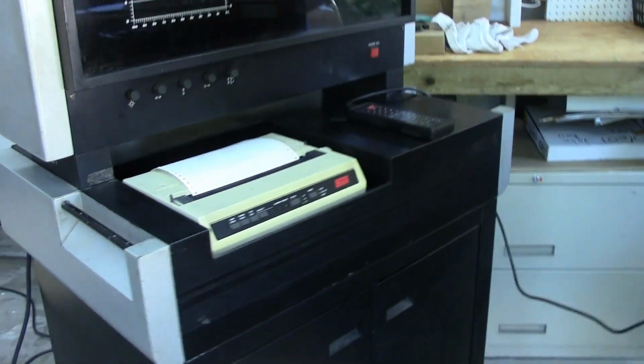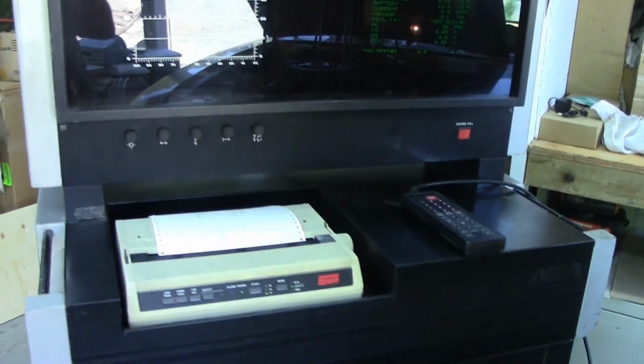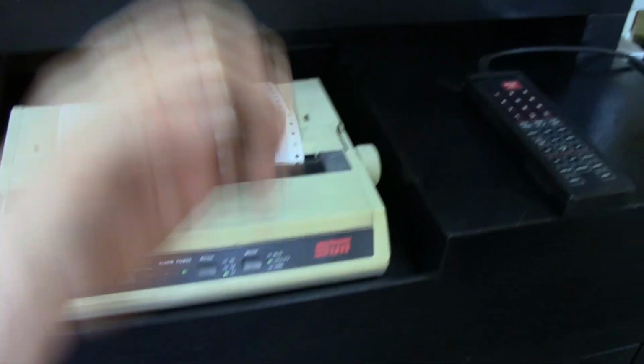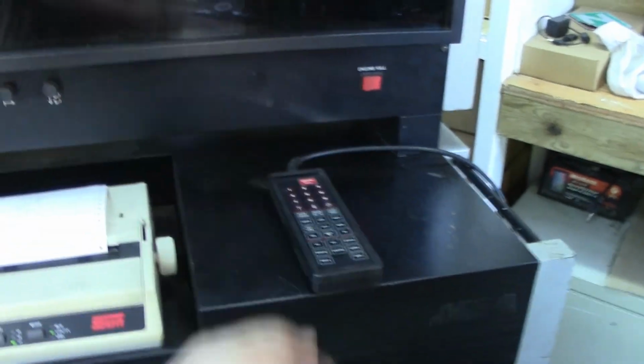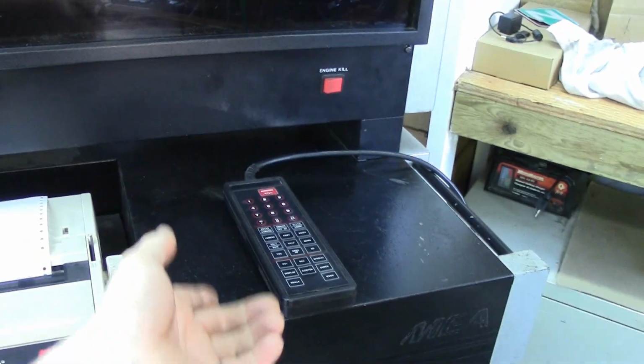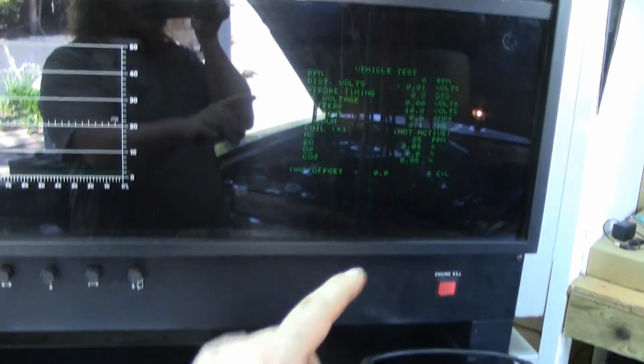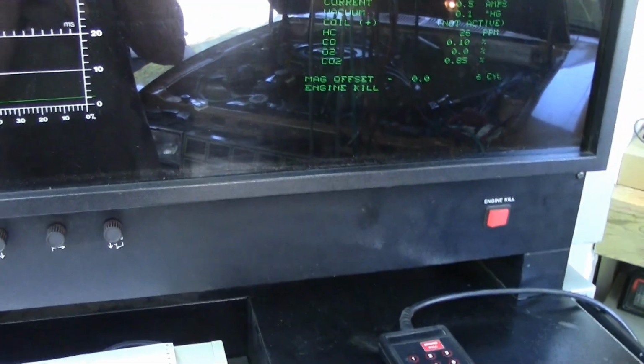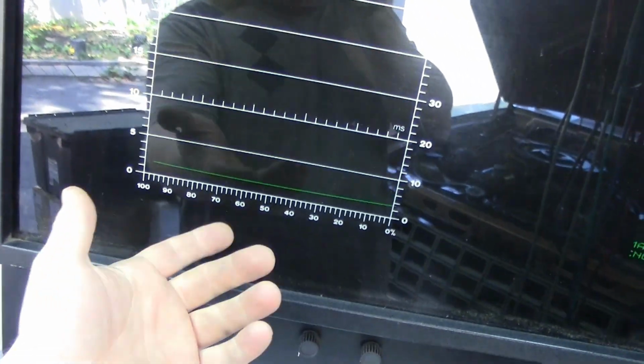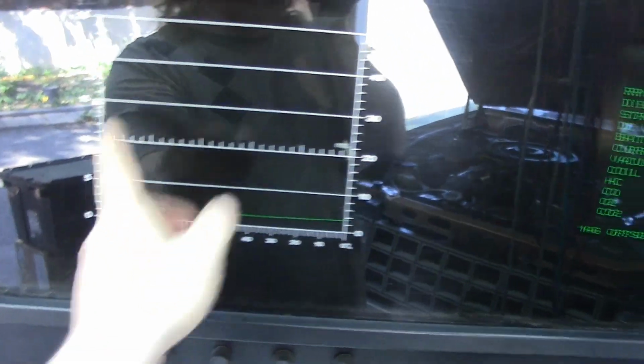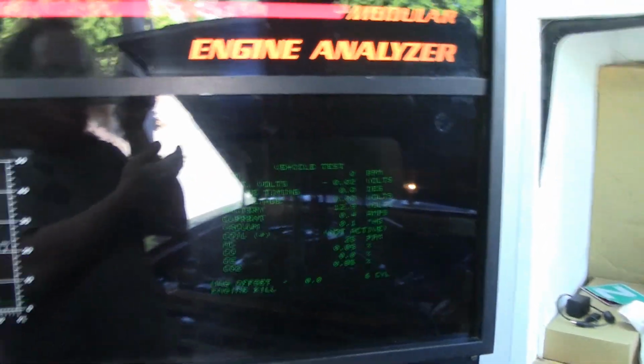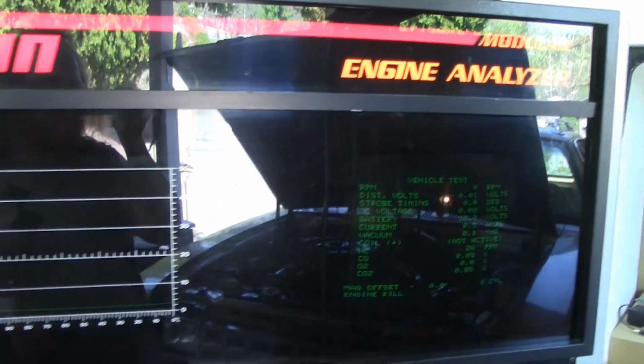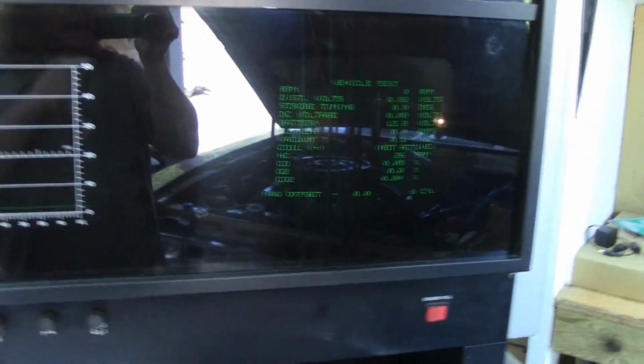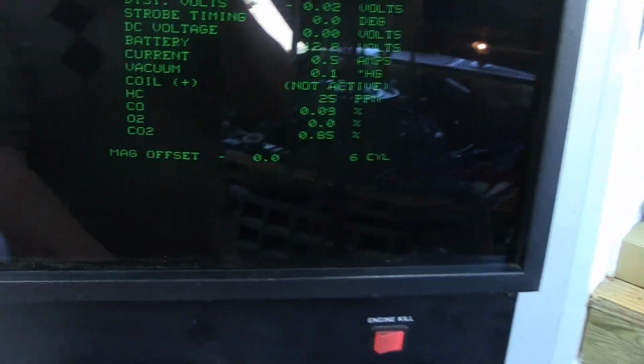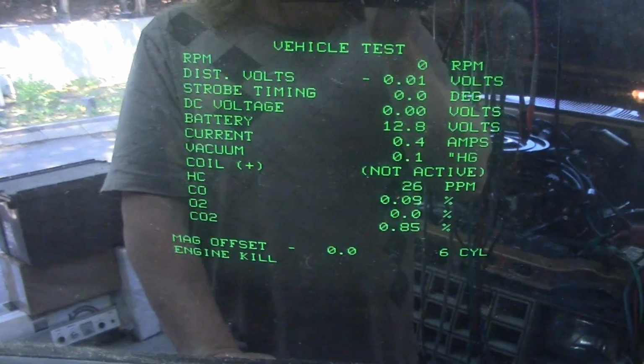And even after all that, there's still the probability that things will go wrong with it. Like, we saw the printer jam up there. We need the O2 sensor, which is going to cost way more than I'll ever use this thing in the remainder of its lifetime. We have the calibration, which means I need to find a calibration gas. We had the fuse, which inexplicably failed and caused part of the unit to not work. Like, any number of things could fail on this, and the service manual is only going to help me so far.